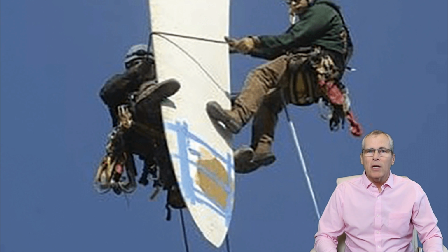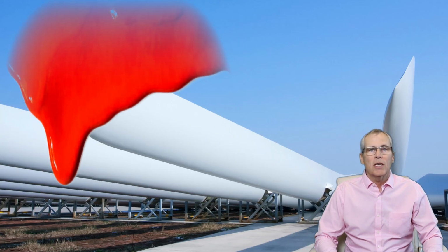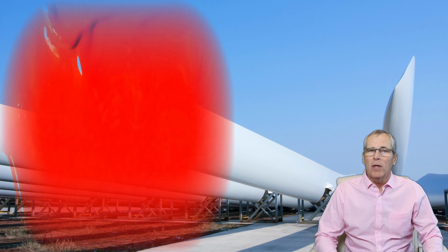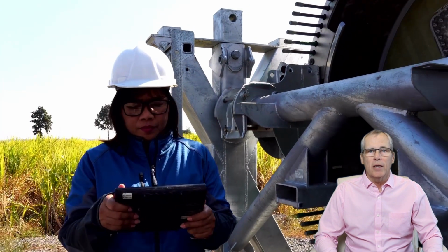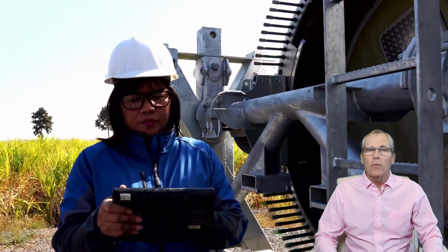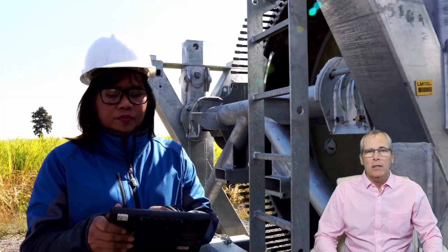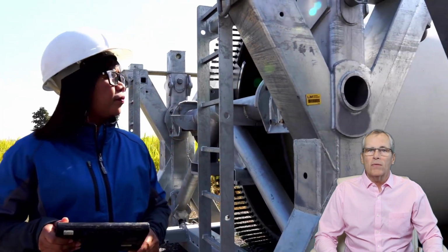To balance the protection of the embedded targets from corrosion versus the reduction in conduction caused by paint, engineers and experts in the field often recommend using specialized coatings, paints that are specifically designed for lightning protection systems. They also recommend regularly inspecting and maintaining the lightning protection to ensure that it is functioning properly and embedded targets are not corroded.